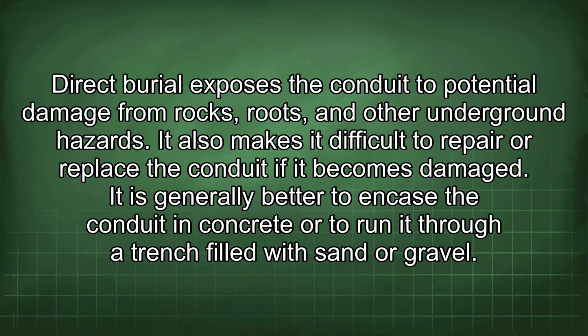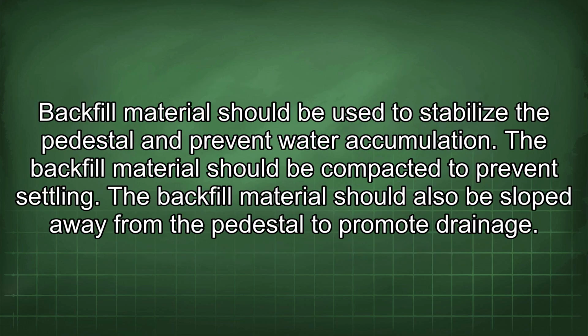It is generally better to encase the conduit in concrete or to run it through a trench filled with sand or gravel. Backfill material should be used to stabilize the pedestal and prevent water accumulation. The backfill material should be compacted to prevent settling. The backfill material should also be sloped away from the pedestal to promote drainage.